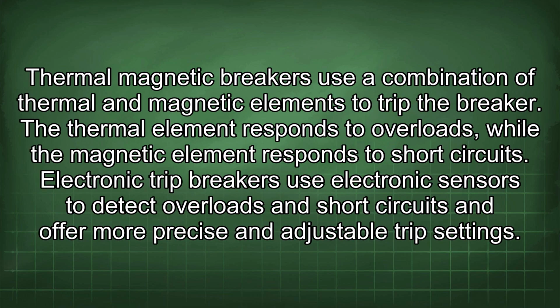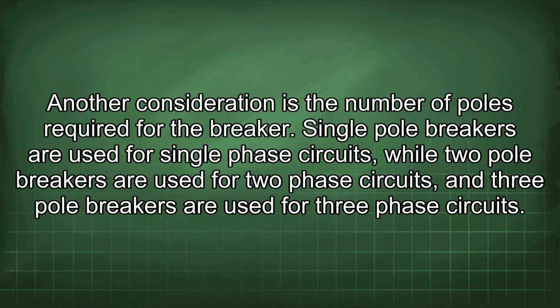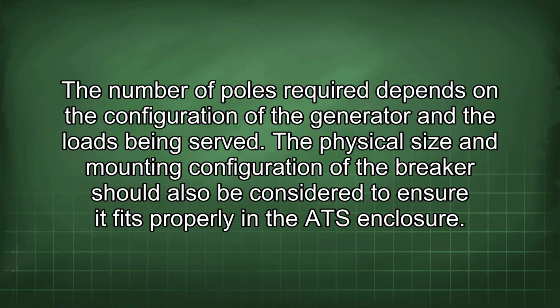Thermal magnetic breakers use a combination of thermal and magnetic elements to trip the breaker. The thermal element responds to overloads, while the magnetic element responds to short circuits. Electronic trip breakers use electronic sensors to detect overloads and short circuits and offer more precise and adjustable trip settings. Another consideration is the number of poles required for the breaker. Single-pole breakers are used for single-phase circuits, while two-pole breakers are used for two-phase circuits, and three-pole breakers are used for three-phase circuits. The number of poles required depends on the configuration of the generator and the loads being served.